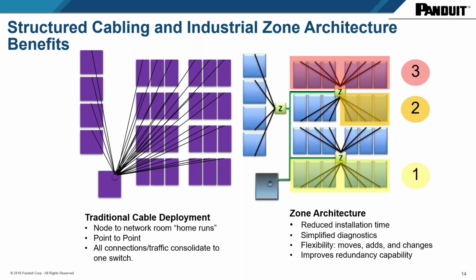That means that you would need to run 6 cables from area 3 back to the center in a star architecture, as you see on the left-hand side. And this type of cable will have to be a level 3 rated cable. So you have 1, 2, 3, 4, 5, 6 rated level 3 cables in all of its MICE rating that have to run the length to get it to the central system.